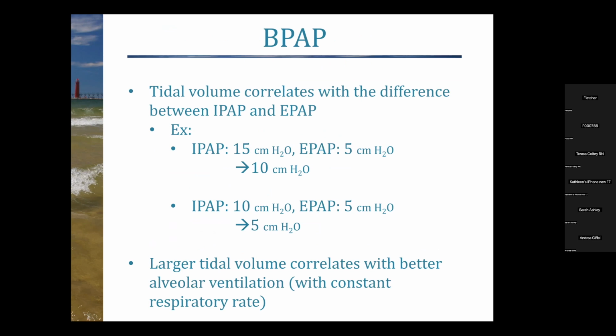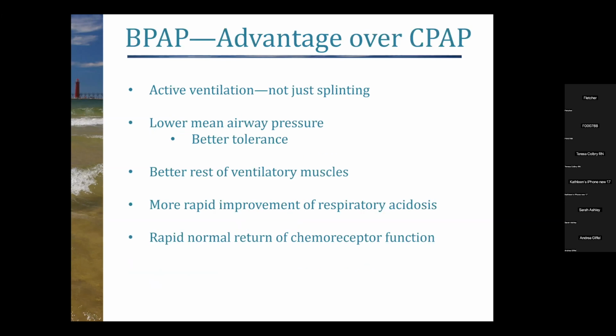With the BiPAP, because we're varying that pressure, the tidal volume is going to vary a little bit as well. So just as an example here, if you set that inspiratory pressure to 15 and the expiratory pressure to 5, that difference of 10 centimeters of H2O is going to determine that volume for you. Versus an IPAP of 10 with an EPAP of 5, you're only getting that 5 centimeters of H2O. So a smaller overall tidal volume there. The advantage of the BiPAP over the CPAP is it's active ventilation, so we're not just splinting the airway open. There's a lower mean airway pressure, so we have less of that high pressure, so patients tolerate it better. And it rests the ventilatory muscles. Muscles don't have to work so hard to exhale. We can see that it'll actually help improve respiratory acidosis and more normal return of the chemoreceptor function. So overall, if you have the choice, BiPAP may be better for the patient than CPAP.